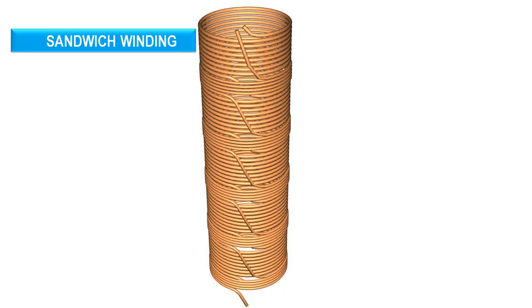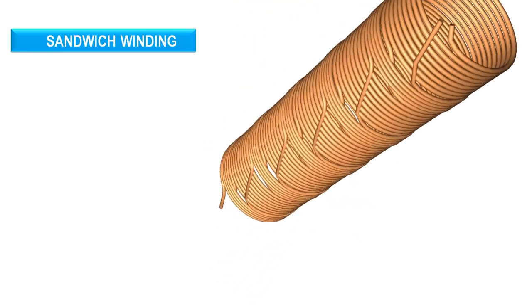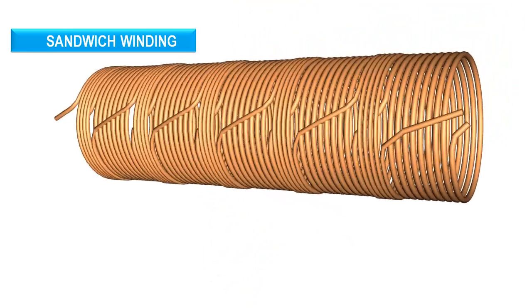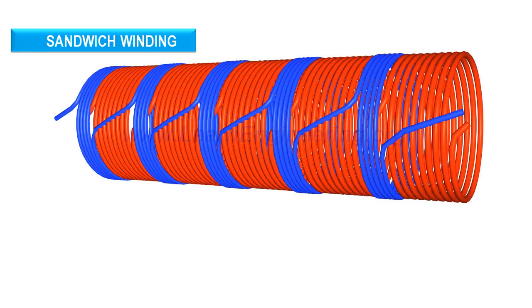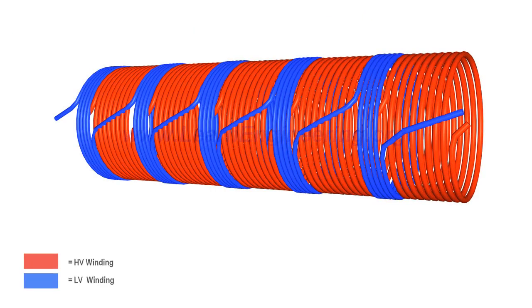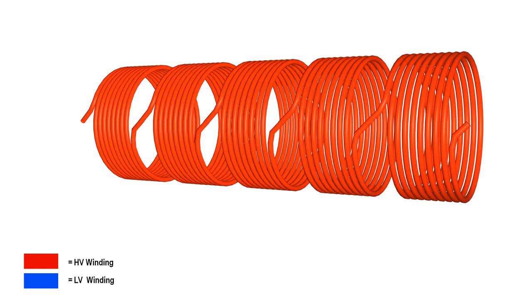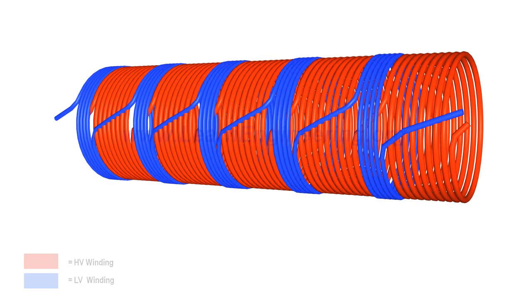Sandwich windings use a unique configuration. Here, high voltage and low voltage windings sit in the same magnetic axis, and each high voltage unit lies between two low voltage units. Thus, the leakage flux is greatly reduced.